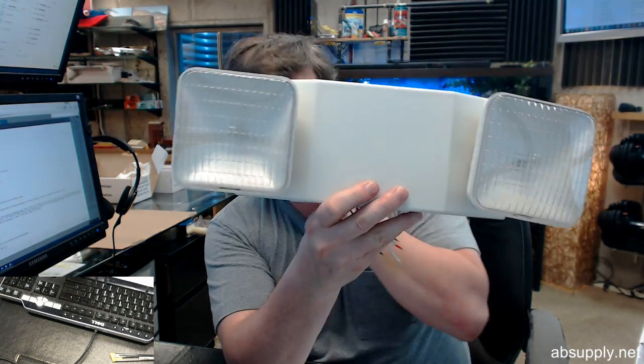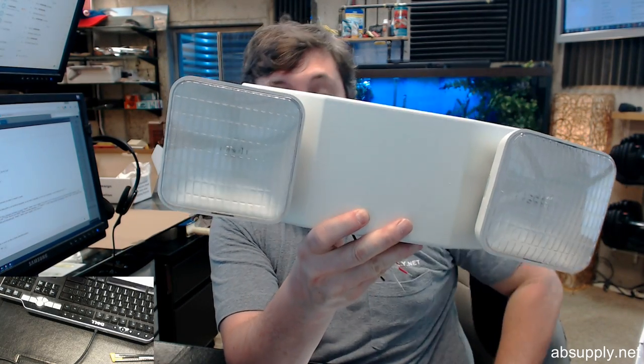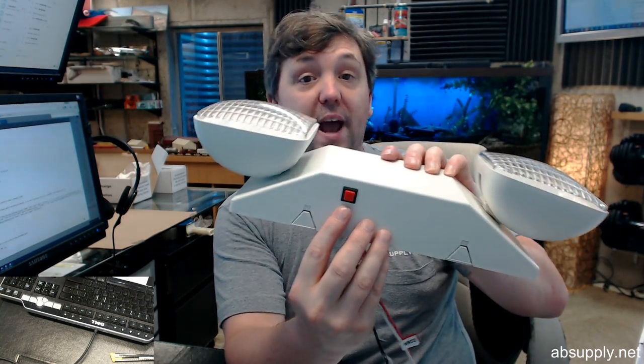Apply power to the unit after it's installed. The LED indicator down on the bottom near the test switch should turn red. You're going to want to leave it alone for 2 hours. Let the battery charge. Test the unit by pushing the switch. The LED indicator should turn off and the lamps should come on. When the switch is released, the lamps turn off and the LED indicator comes back to red.